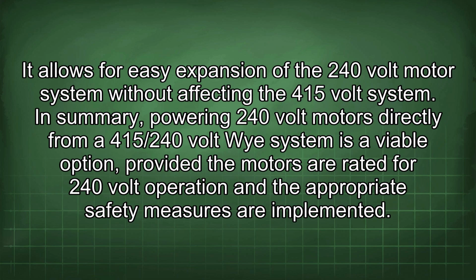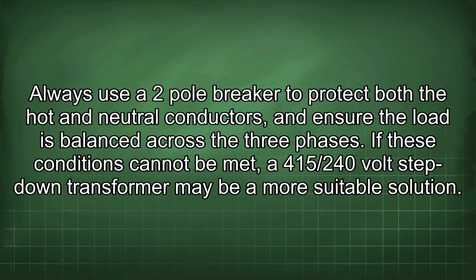In summary, powering 240-volt motors directly from a 415/240-volt Y system is a viable option provided the motors are rated for 240-volt operation and the appropriate safety measures are implemented. Always use a 2-pole breaker to protect both the hot and neutral conductors and ensure the load is balanced across the 3 phases. If these conditions cannot be met, a 415/240-volt step-down transformer may be a more suitable solution.